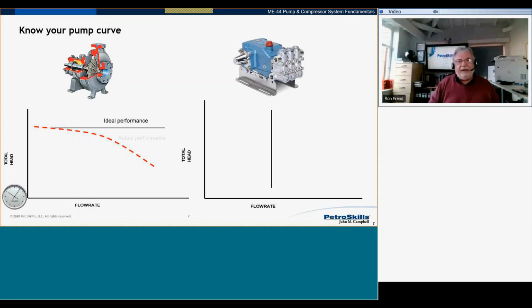You're going to get something like this. It's going to depend on specific speed and all sorts of other things. You can change that pump curve by changing the speed or changing the impeller diameter. So this is important to know. And when we're looking at the pump curve, we've got a curve with a vertical axis, which is head. You could use pressure, but we tend to use head. The bottom axis is volumetric flow rate.